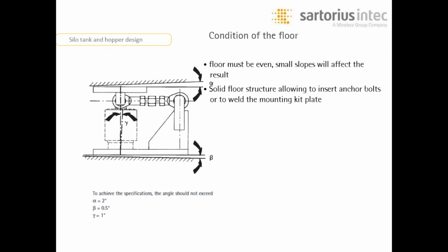For best results and highest accuracy, it is very important that the mounting kits be installed with the top and bottom plates level to one another directly under the vessel foot. Floor must be even. Small slopes will affect the result. It is very important that these are shimmed so that they are completely level to one another.